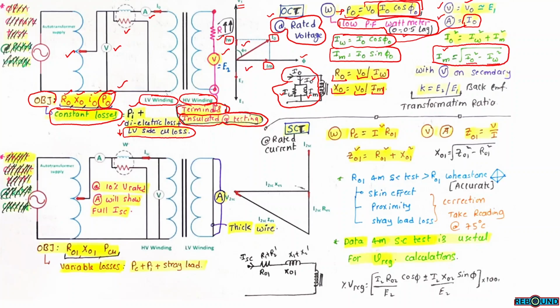The voltmeter on the secondary side will read the back EMF E2. So this is the term E2 and this is the term E1. The voltmeter on the secondary will read the back EMF E2. Transformation ratio K can be calculated from this open circuit test condition. K equals E2 by E1. The voltmeter on the HV side will give you E2. The voltmeter on the LV side can be approximately considered as E1. So from the open circuit test, R0, X0, I0 and P0 are calculated.